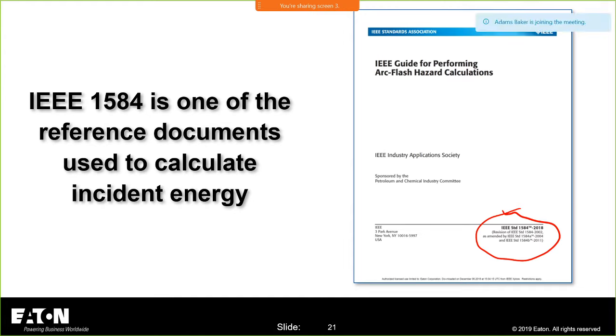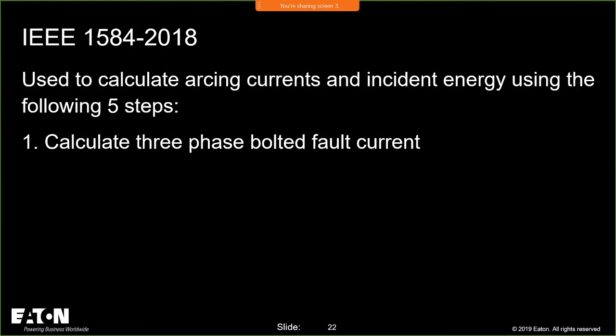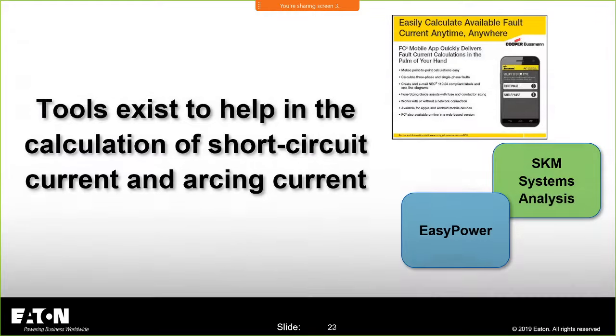Now, when we calculate incident energy and why we have to understand clearing times, we're using IEEE 1584 to do our calculations. The latest version is the 2018 version. 1584 tells us that we need to calculate three-phase bolted fault currents to understand what's going on, and we have lots of tools on the market available to help us do that. From free tools to tools like SKM, EDSA, Easy Power, all of those different software applications, there is no reason why you can't determine or estimate the amount of fault current at any point in a power distribution system.